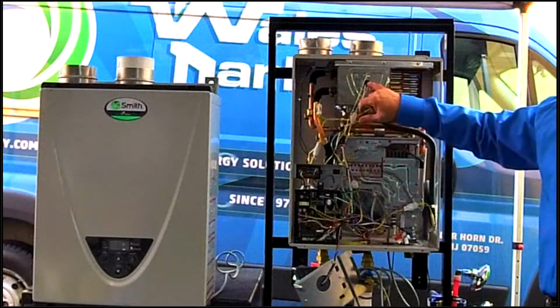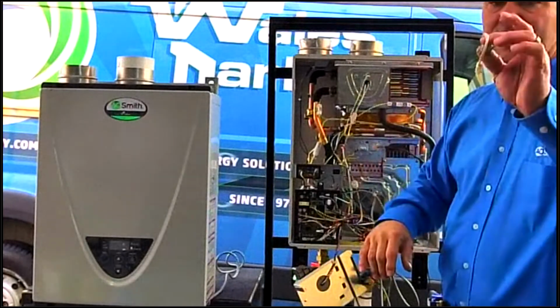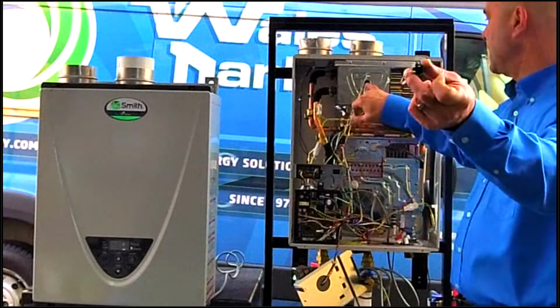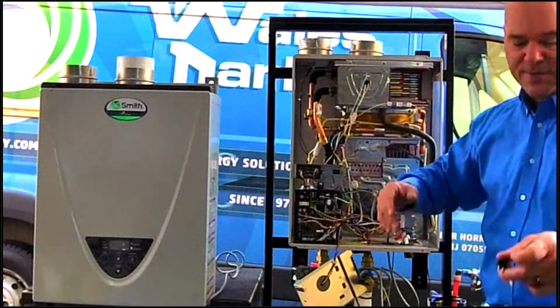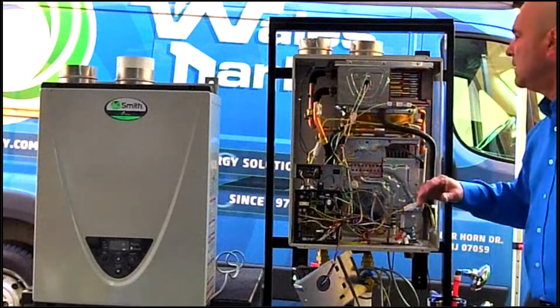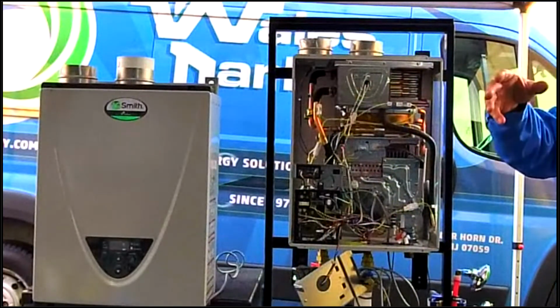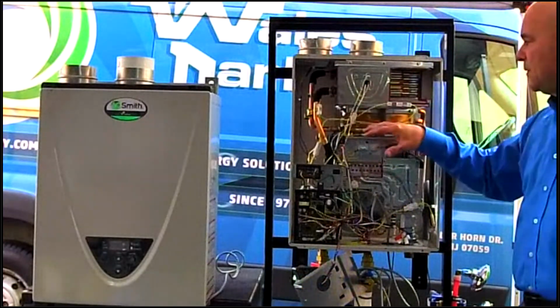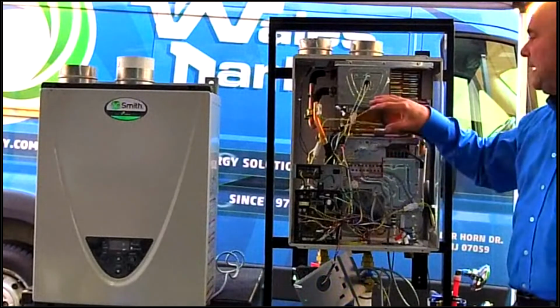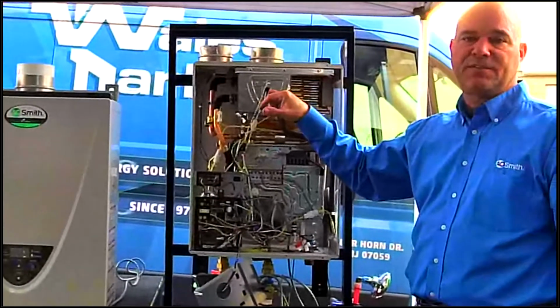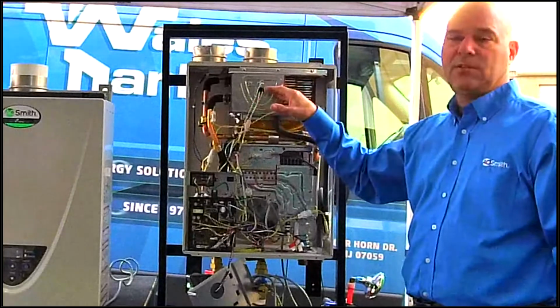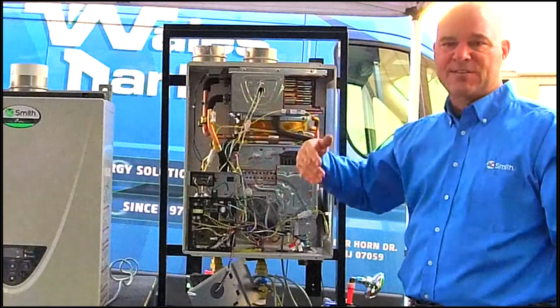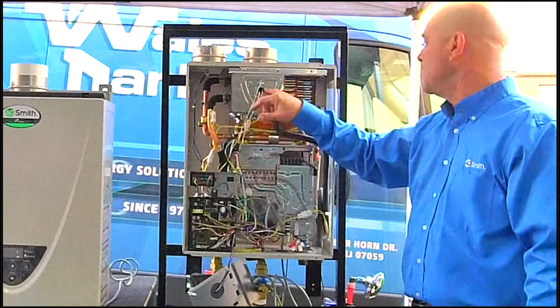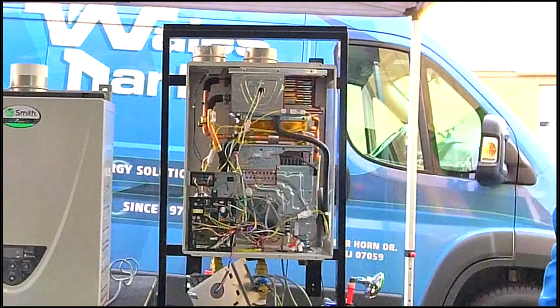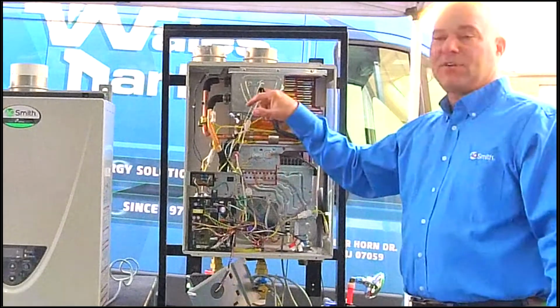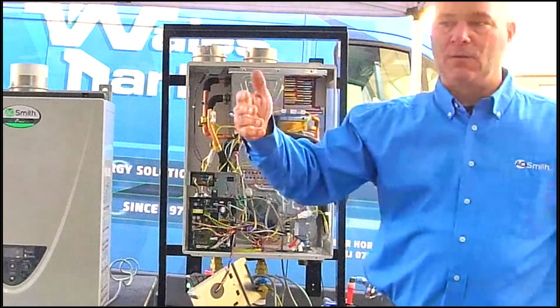Right here, this is a Klixon sensor. This is a 157-degree sensor. This is an automatic reset. So if for some reason we had a tremendous amount of wind outside and someone was using the tankless water heater and the sensor felt 157 degrees, it would shut the unit down. It would do an auto reset. And after the auto reset, the unit would fire back up on its own.